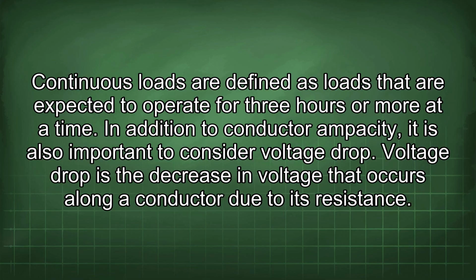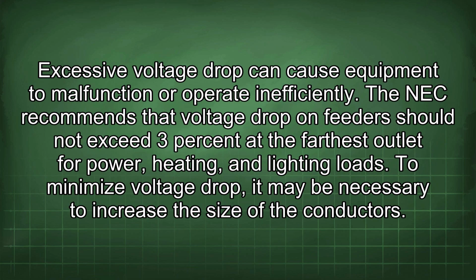In addition to conductor ampacity, it is also important to consider voltage drop. Voltage drop is the decrease in voltage that occurs along a conductor due to its resistance. Excessive voltage drop can cause equipment to malfunction or operate inefficiently. The NEC recommends that voltage drop on feeders should not exceed 3% at the farthest outlet for power, heating, and lighting loads. To minimize voltage drop, it may be necessary to increase the size of the conductors.